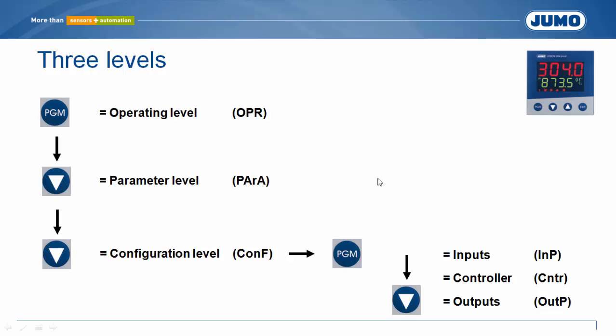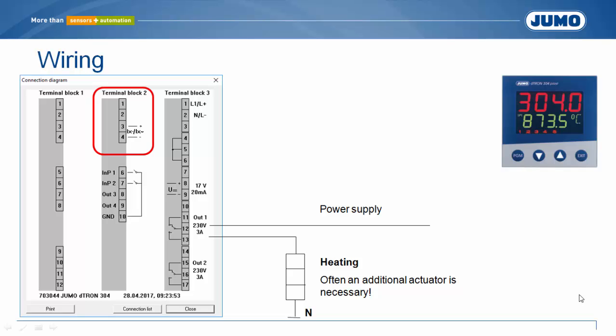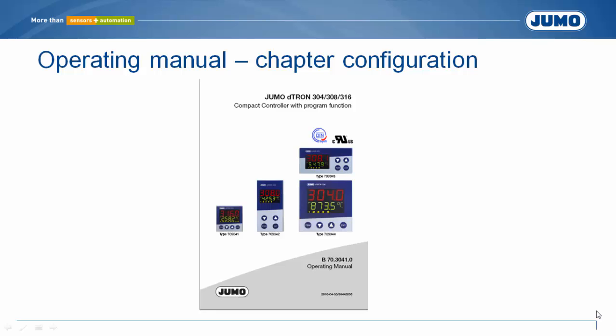The compact controller has 3 levels: operating level, parameter level and configuration level. For many applications, the configuration of the submenus Inputs, Controller and Outputs is sufficient. The following application generally complies with the factory settings. But a transmitter with range 4 to 20 mA provides a temperature signal. This corresponds to a temperature range of 0 to 200 centigrades. The settings must be done in the menu Inputs in the configuration level. The manual for the d-tron serves as an addition.